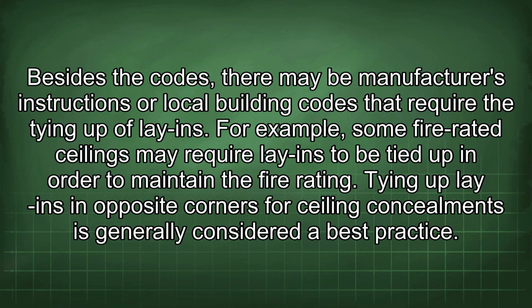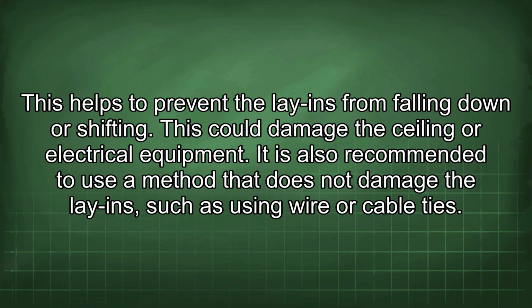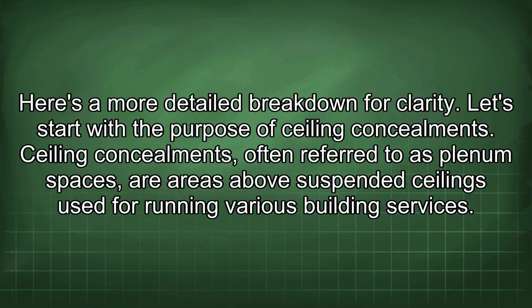Besides the codes, there may be manufacturers' instructions or local building codes that require the tying up of lay-ins. For example, some fire-rated ceilings may require lay-ins to be tied up in order to maintain the fire rating. Tying up lay-ins in opposite corners for ceiling concealments is generally considered a best practice. This helps to prevent the lay-ins from falling down or shifting. This could damage the ceiling or electrical equipment. It is also recommended to use a method that does not damage the lay-ins, such as using wire or cable ties. Here's a more detailed breakdown for clarity.